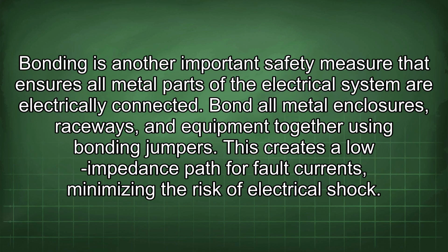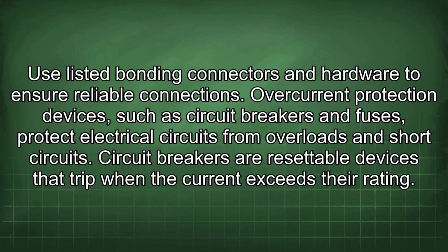Bonding is another important safety measure that ensures all metal parts of the electrical system are electrically connected. Bond all metal enclosures, raceways, and equipment together using bonding jumpers. This creates a low impedance path for fault currents, minimizing the risk of electrical shock. Use listed bonding connectors and hardware to ensure reliable connections.